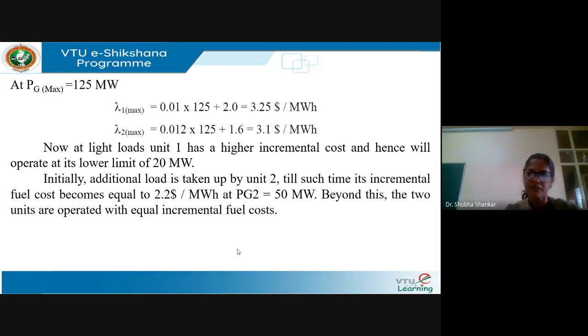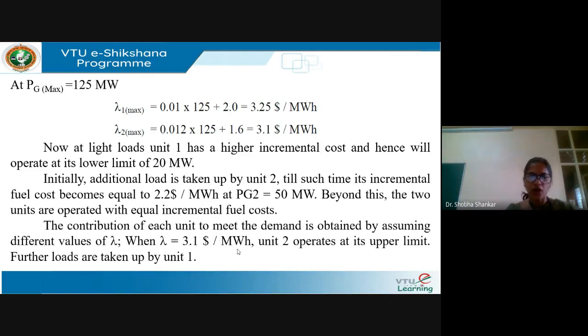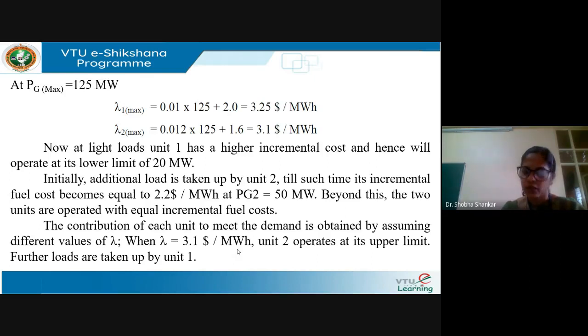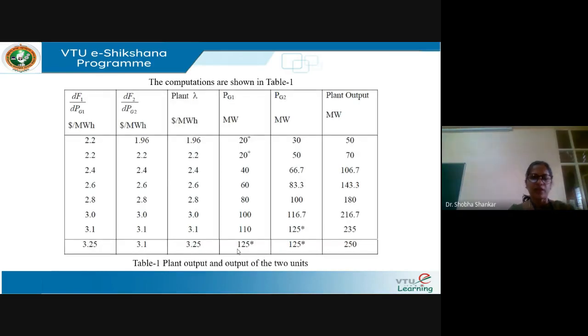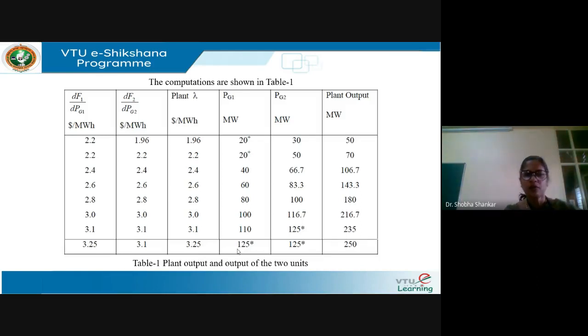Beyond PG2 = 50 MW, the two plants are operated with equal incremental fuel costs. The contribution of each unit is obtained by assuming different values of lambda. When lambda = 3.1 $/MWh, unit two operates at its upper limit and further loads are taken up by unit one. The table shows plant output, incremental fuel costs for both plants, power output of each plant, and total plant output.